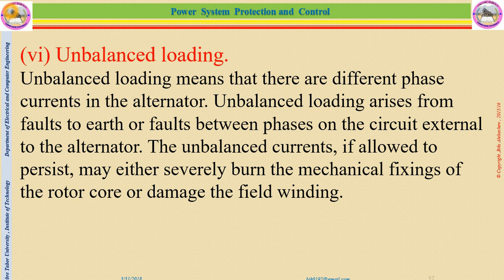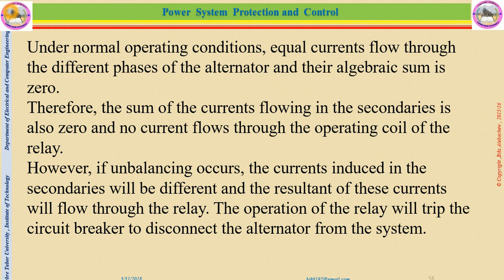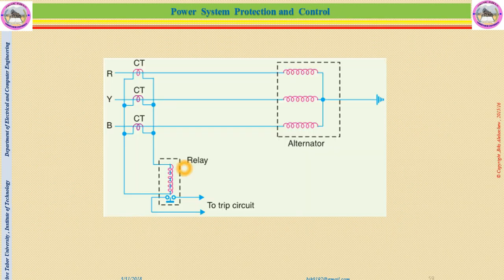Now let us see the protection mechanism. Under normal operating conditions, equal current flows through the different phases of the alternator, and their algebraic sum is 0. Therefore, the sum of the currents flowing in the secondary is also 0, and no current flows through the operating coil of the relay. However, if unbalancing occurs, the currents induced in the secondary will be different, and the resultant current will flow through the relay. So the sum of the currents may not be 0. The operation of the relay will trip the circuit breaker to disconnect the alternator from the system. This is one of the protection mechanisms for an unbalanced system.